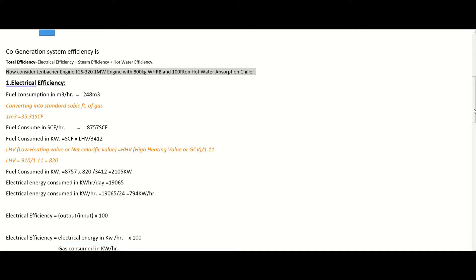Steam and chilled water are basically byproducts of the gas generator. As you already know, efficiency is output divided by input. For electrical efficiency, the output is electricity and the input is gas. For waste heat recovery boiler efficiency, the output is steam and the input is natural gas. For the hot water absorption chiller, the output is chilled water and the input is gas, because the only running source is natural gas. So the total efficiency of the cogeneration system is the sum of electrical efficiency, steam efficiency, and hot water efficiency.